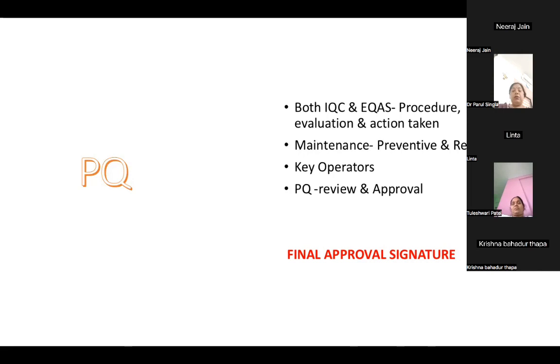Both IQC and EQAS can be used. IQC can be done for 10 days. Accuracy can be checked for all the levels, level 1 and level 2. Then an EQAS sample can also be processed and checked. What was your last EQAS achieved? You can evaluate how the EQAS performance is. And if it is not behaving properly, you can do an inter-lab comparison or inter-instrument comparison.